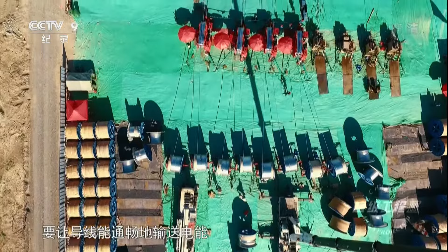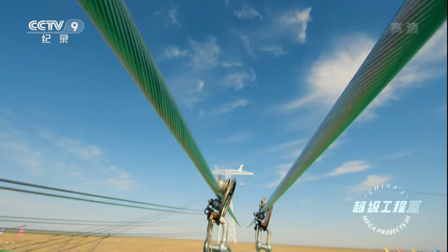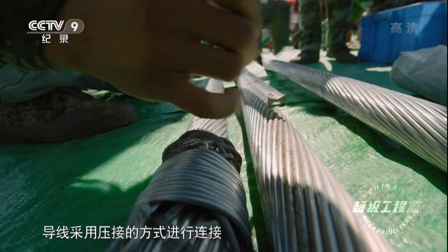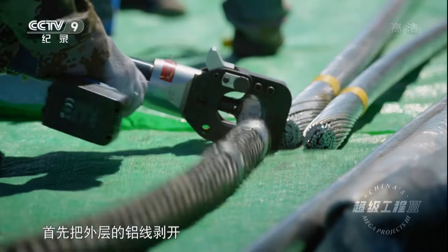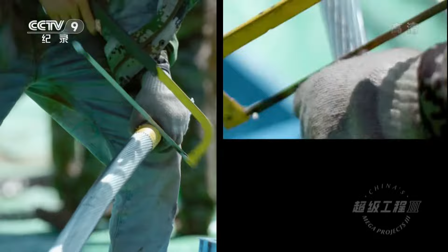To ensure the transmission runs smoothly and efficiently, the 20,000 conductor joints have to be connected perfectly. The cables are connected by intense pressure. First, the outer aluminum wires are stripped back to expose the steel core. Then the two ends of the steel core are inserted into a metal sleeve.